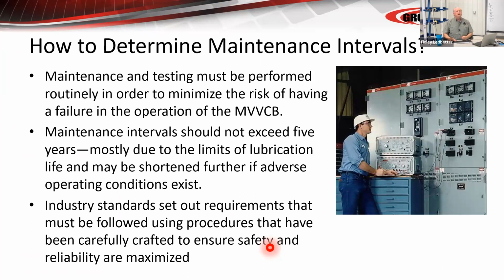Basically, we've said it's got to be performed in some routine. You're risking failure if you don't. I don't think maintenance intervals should exceed 5 years generally. There are always changes to limits. Some should obviously be faster. There are probably some arguments for a little longer, mostly due to the limits on lubrication. Life might be shortened further if adverse operating conditions exist: humidity, temperature, repetitive duty, poorly applied.